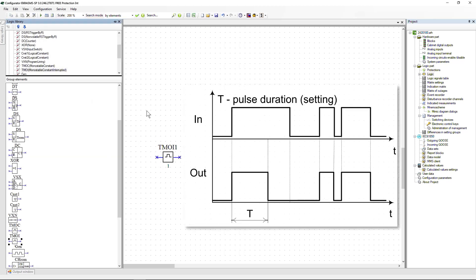Pulse former with interruption: generates a pulse similar to the pulse former, but if the input signal goes from logical one to zero before the specified setting, then the pulse at the output of the element also goes to logical zero.